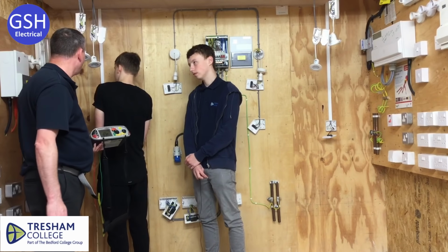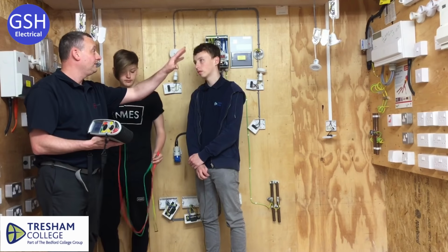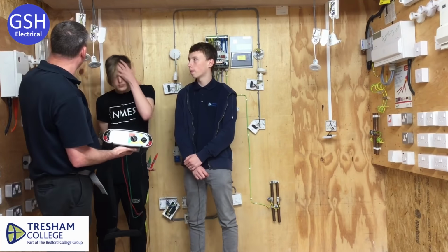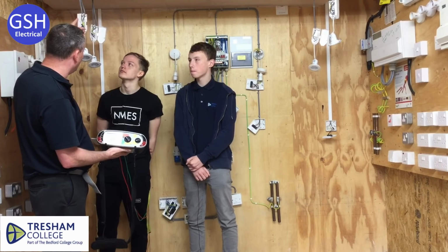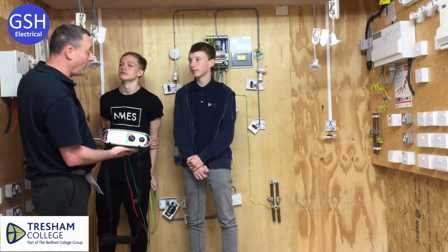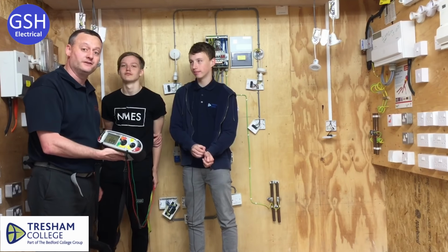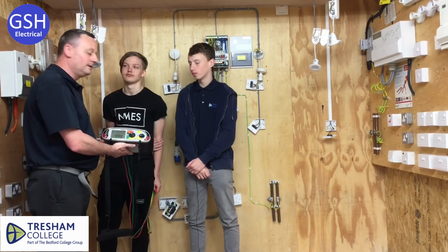Which test is carried out next, Harrison? Insulation resistance. In order to do the insulation resistance test, what are we going to have to do with the lighting points themselves? Take the loads off. We took the loads off and we've disconnected, in this case, the line in every one of the joint boxes, so we can carry out the insulation resistance test. We're going to do the insulation resistance test next, then we're going live. Okay, let's move on to that.